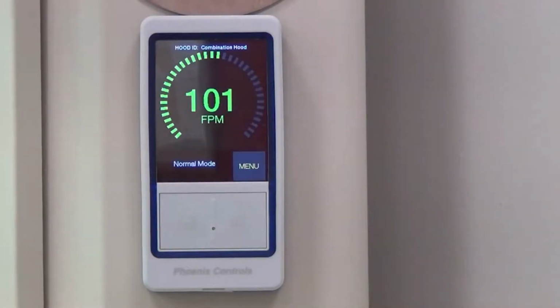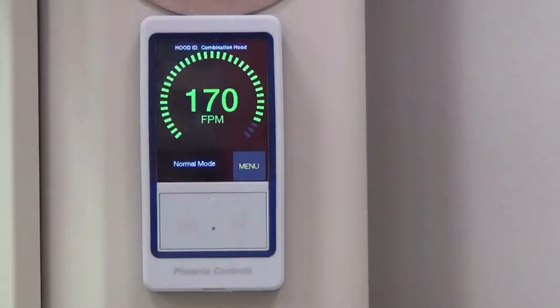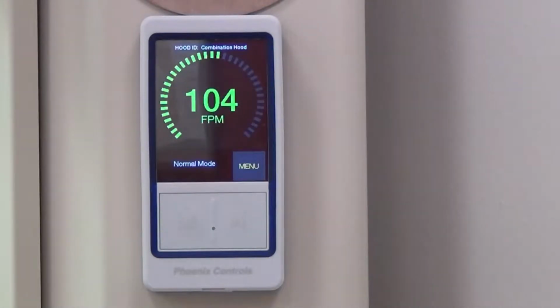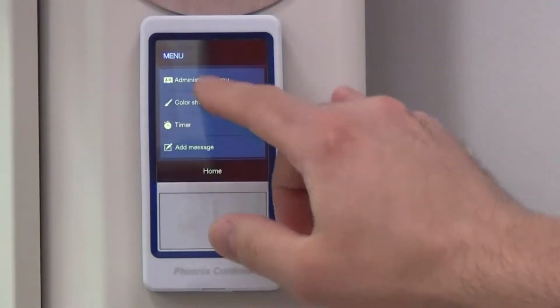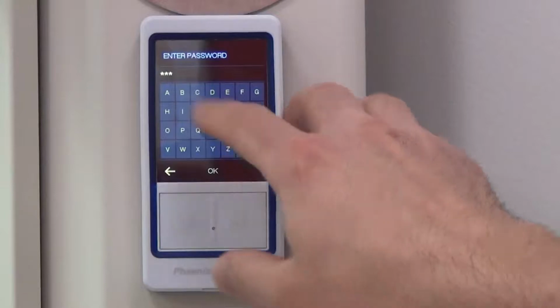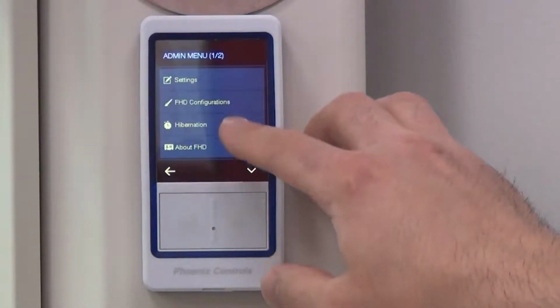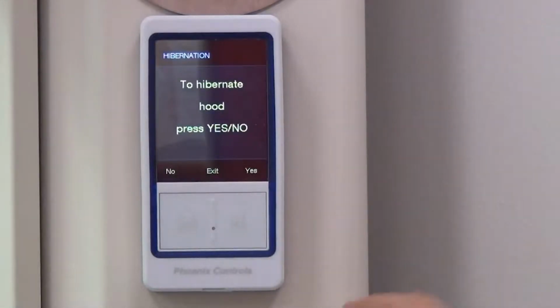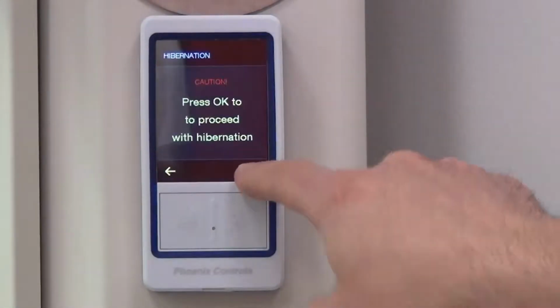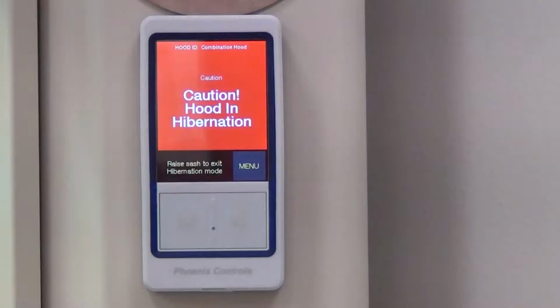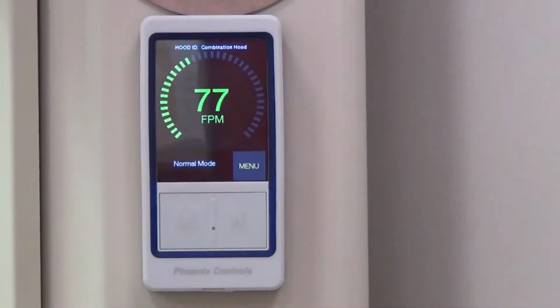So those are just some of the features of the new Century Fume Hood display. Just like the previous monitor that I used on the other wet chemistry lab with the smoke in it, this one also has the ability to go into hibernation mode. It's a little bit different method than the other one, but if I go in through the menu and the admin menu, punch in my password, and go into hibernation mode, it'll say, do you want to hibernate the hood, yes or no? I push yes, it says press OK to proceed, waiting for hibernate operation, and now you can see that it clearly shows the fume hood is in hibernation. Again, if I move my sash open, within a second that fume hood is going to respond and it's going to come out of hibernation mode and go back into its normal operation. So same functionality, plus a lot more inside this monitor versus what we had in the past.